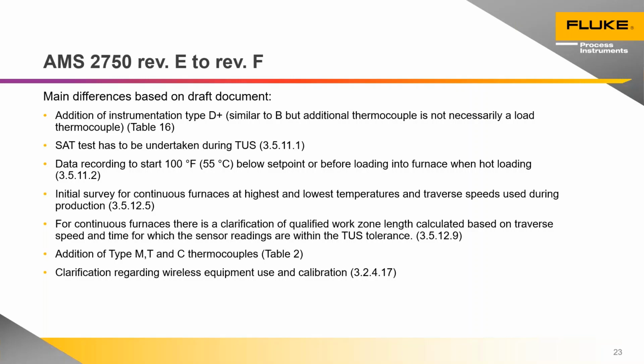Datapaq can make the data loggers available with a wide range of thermocouples. In fact, we already have type T loggers in use. And there's been a clarification regarding use of wireless equipment, and it doesn't affect us in that the piece of equipment that needs to be sent back for calibration is the one with the analog to digital conversion in it. That is our data logger that contains the radio equipment. So continue as is. It's only the data logger that needs calibration, not the full wireless chain of receivers and transmitters.